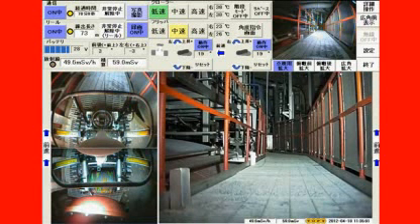The utility says there were no leaks or traces of leaks in manholes on the chamber where leakage had been suspected. But TEPCO has not been able to confirm the conditions of pipes connecting the suppression pool and the containment vessel, where the company also suspects water is leaking.